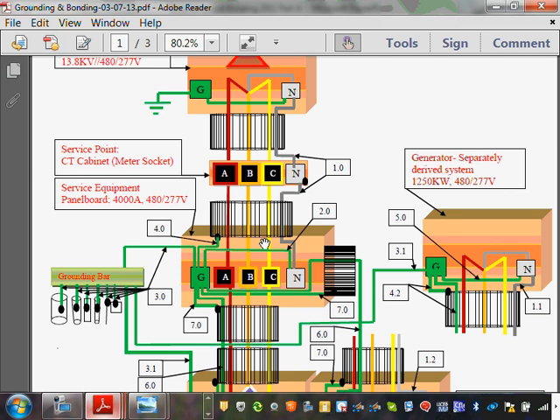What we're trying to do is create what they did here: tying my equipment to Mother Earth. These are called grounding electrode systems, tied together, coming to my switchgear. There are different approved methods, and the NEC book, guys, goes into detail on the approved methods. Any comments about what we're doing here? Ignore all these grounding electrode systems coming here. I have 3.0 because we size them differently.